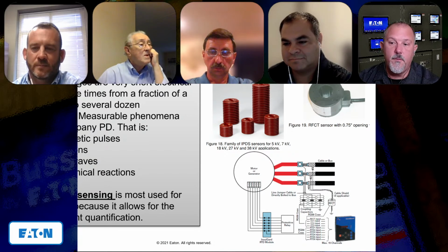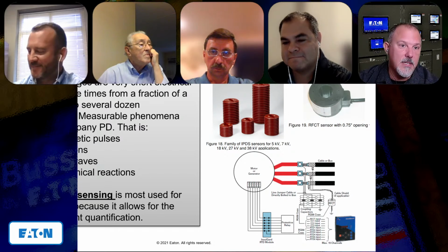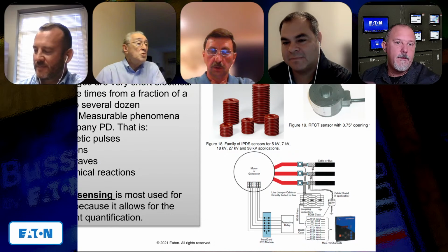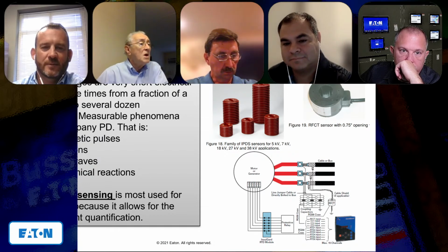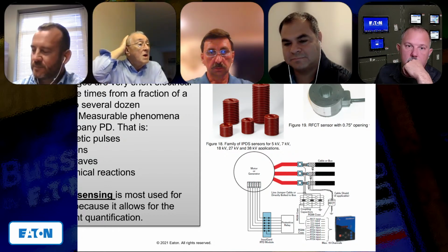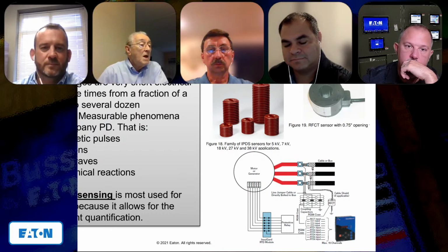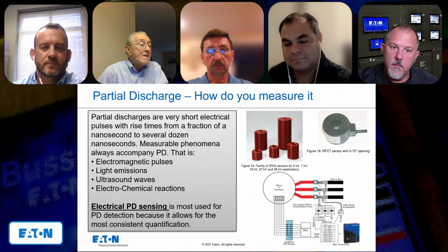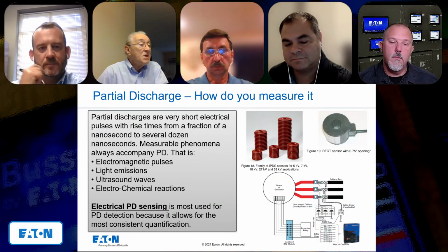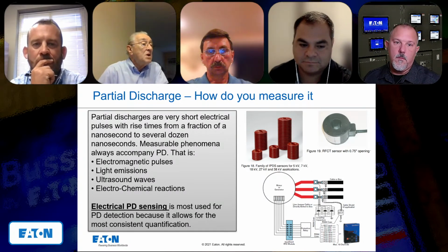And now Muhammad is asking, how long do you need to monitor the equipment before capturing an event, or I guess before determining that you have a problem? Is this something I can put on today and wake up tomorrow morning and say, okay, I've got a problem? Or do I have to wait 6 months, 1 month? Usually deterioration of insulation is a slow process. So we should continuously monitor the condition of the insulation and see whether the partial discharge is stable in this insulation or not.